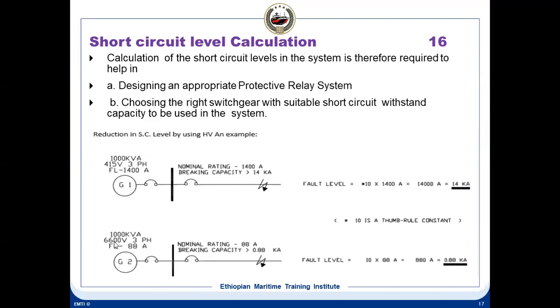Now this generator is having 6.6 or 6600 volt. The full load current is only 88 amps here. The other one, the full load current is 1400 amps. Now this breaker which is here, normal rating is 1400 amps. But breaking capacity has to cater for the fault level, that is 10 times. It is a thumb rule constant multiplied by 1400. That means your total current in this case is going to be 14 kA in case of a fault level. The fault level current is going to be 14 kA. So the breaker has to be rated for 14 kA. Kiloamps, that means 14,000 amps.